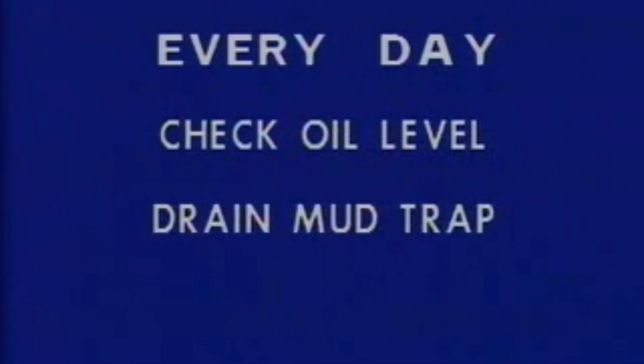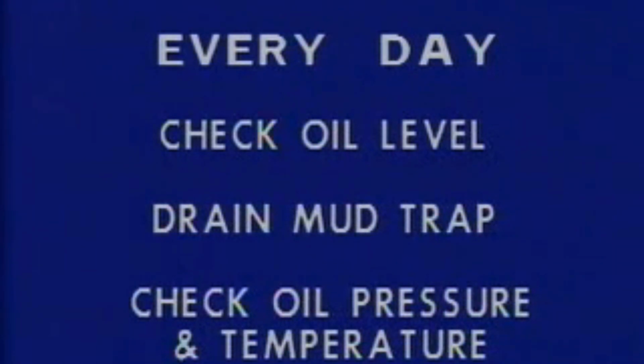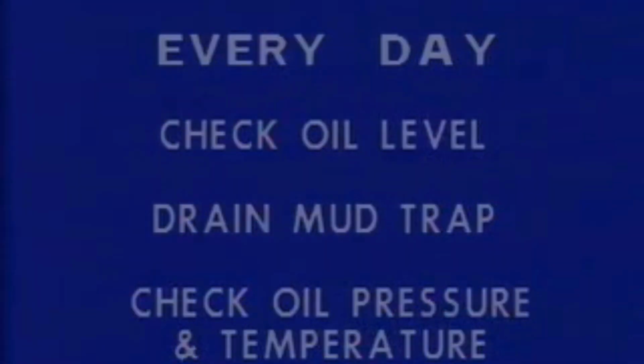Every day, check the oil level. Drain sludge from the mud trap. And check the oil pressure and temperature. Change the filter element every few weeks, sooner if the pressure builds up on the filter inlet. If you're not familiar with all these procedures, rewind the tape and watch it again. Goodbye, good luck, and good pumping.